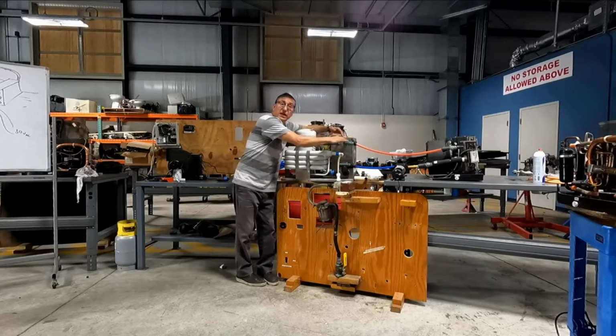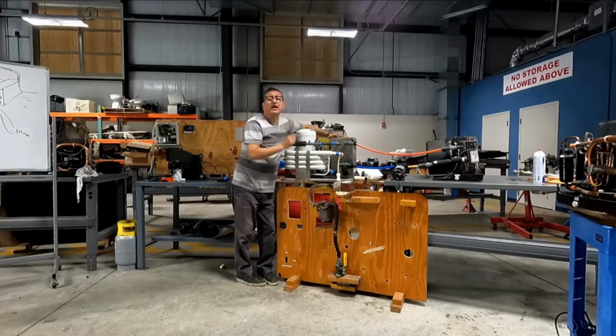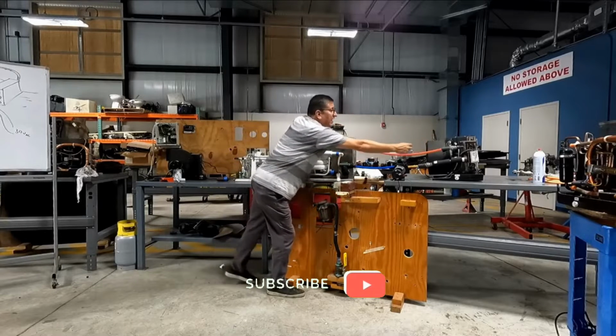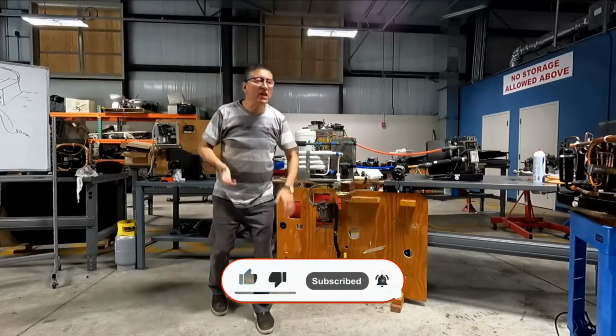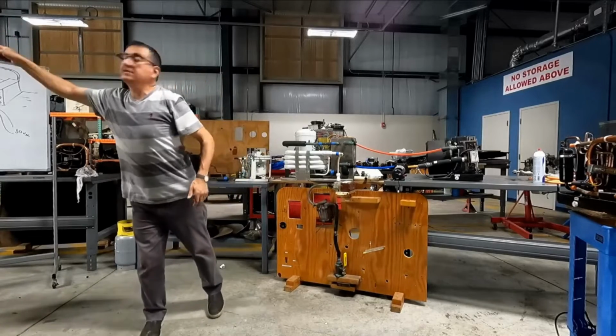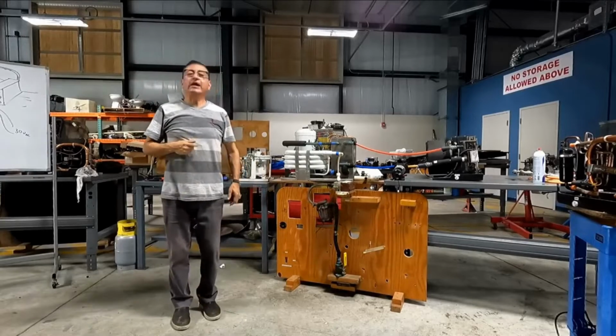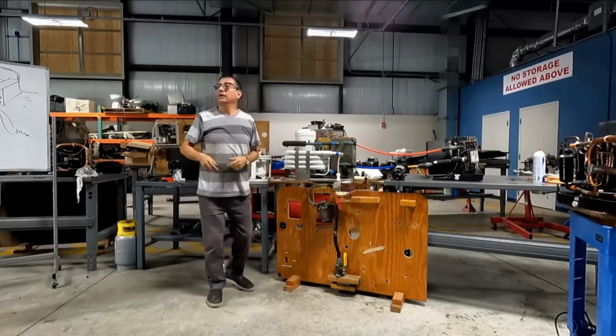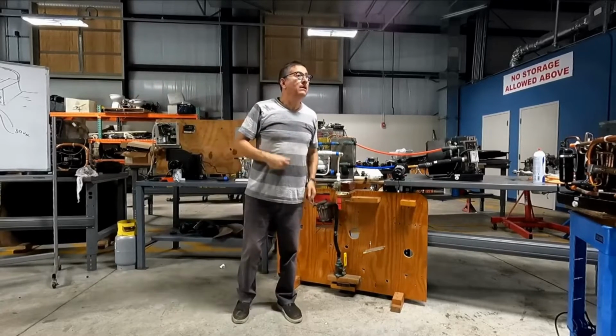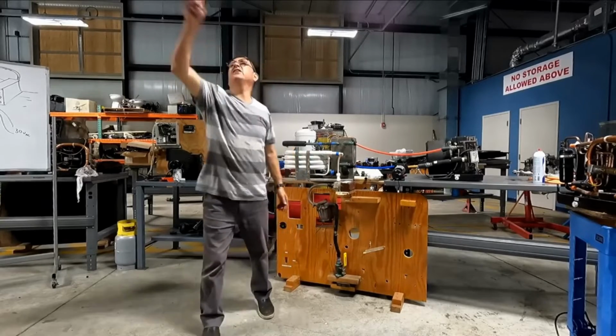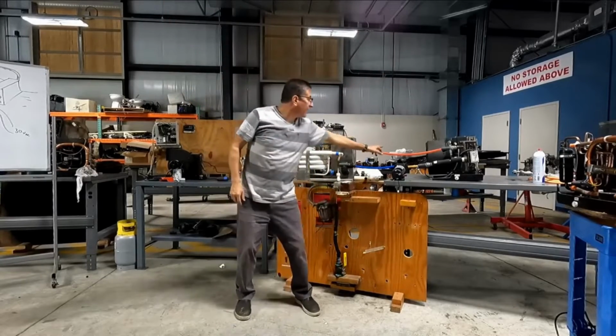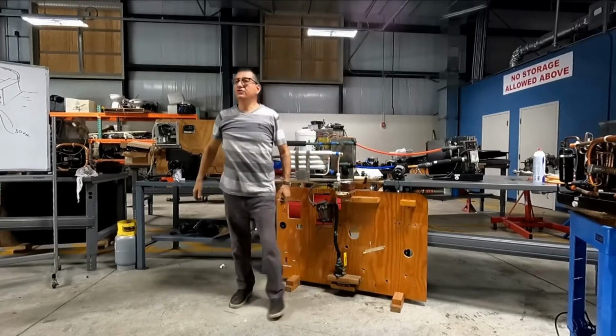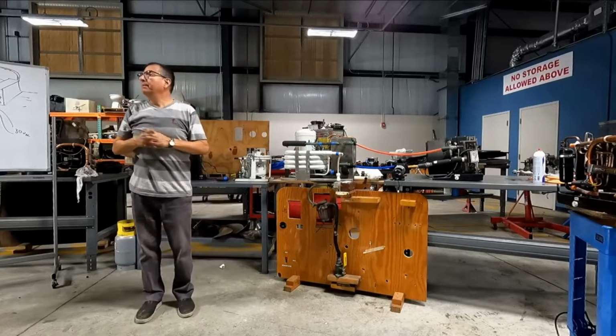The only difference is that the evaporator is surrounded not by air, it's surrounded by fresh water. And that fresh water becomes chilled. And I circulate that chilled water over there and return here. You like it? Yes, I have refrigerant in the central chiller unit located in this building. In the other offices, I have air handlers. The communication between this central unit and the air handlers is with pipes and fresh water. I don't have refrigerant traveling a longer distance. I have fresh water traveling a long distance. Anybody follow me? Yes.